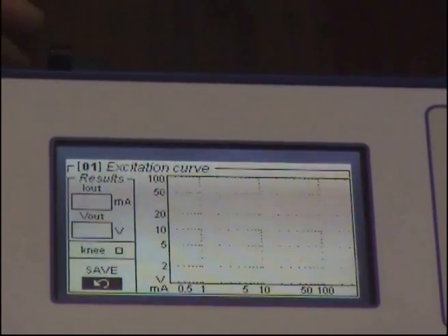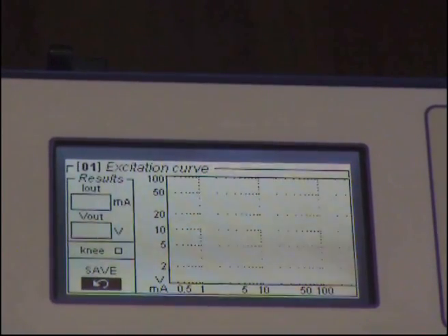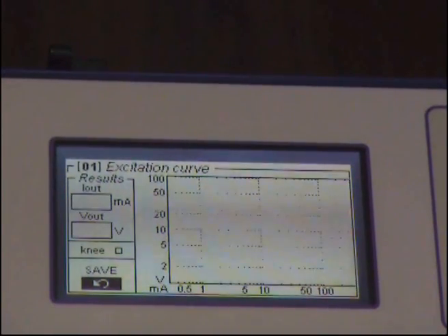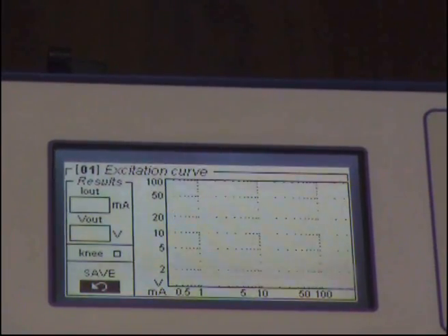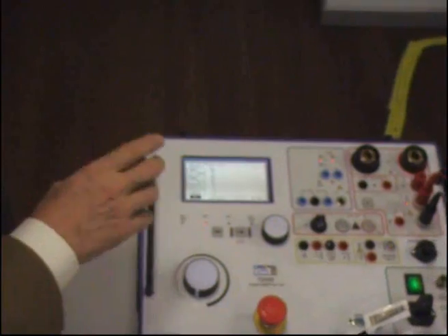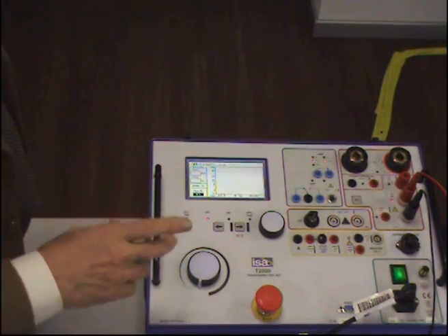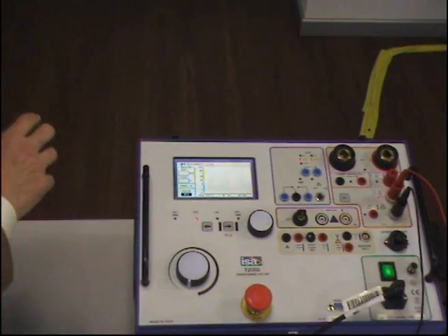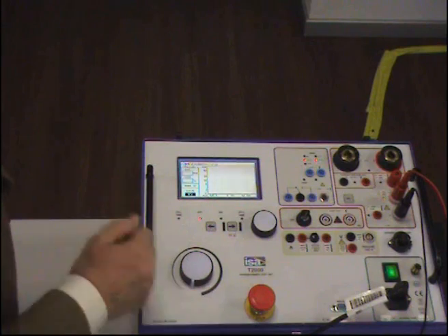There is one important thing to note: you have to move the current control knob slowly, because otherwise you would cause a saturation effect on the current transformer that will also cause some shift in the knee point. The knee point will not change much if you are slightly fast, but if you are too fast it will change.